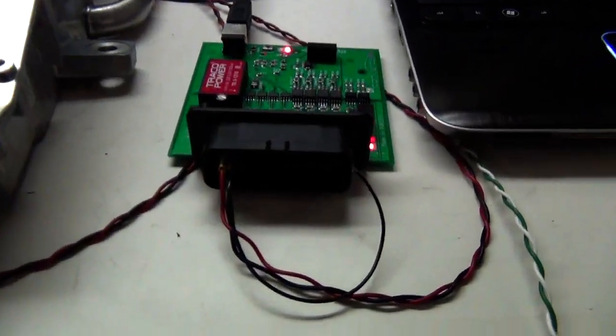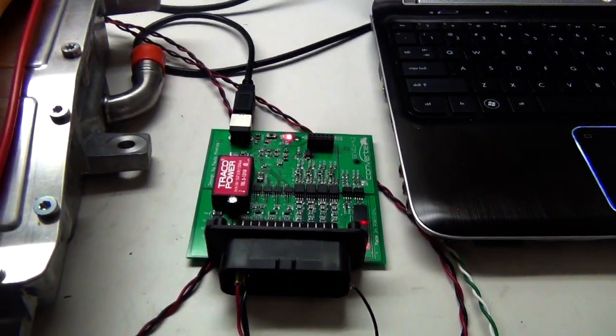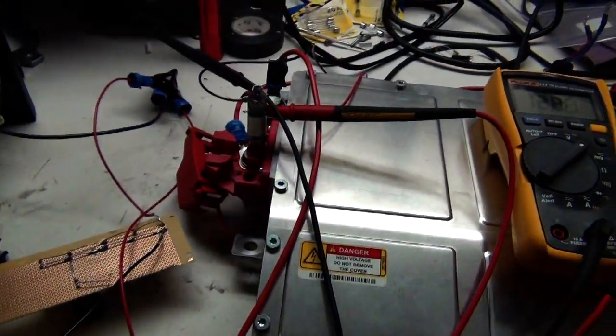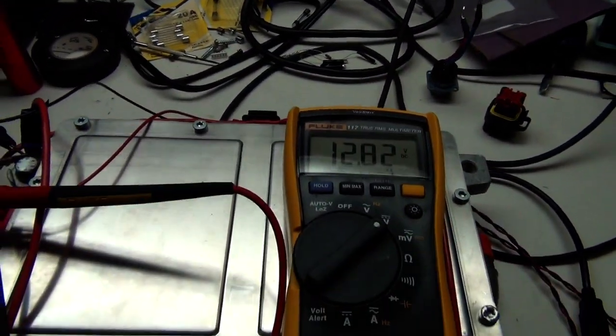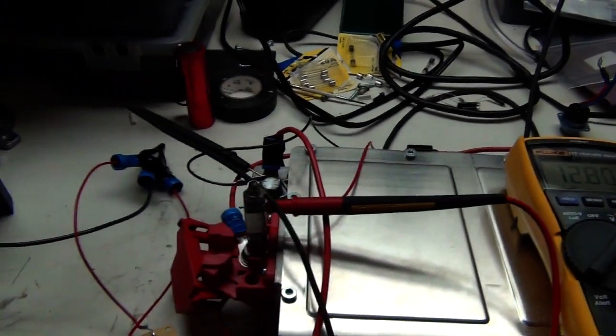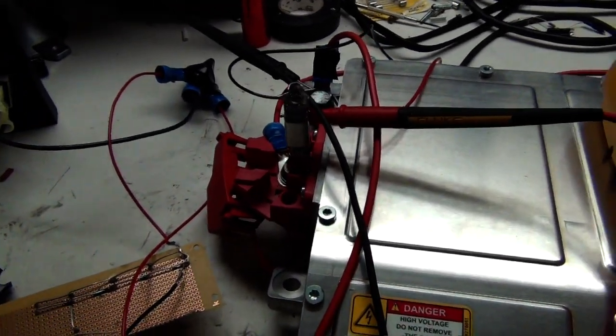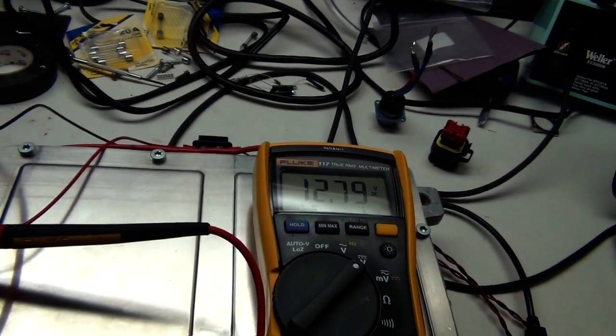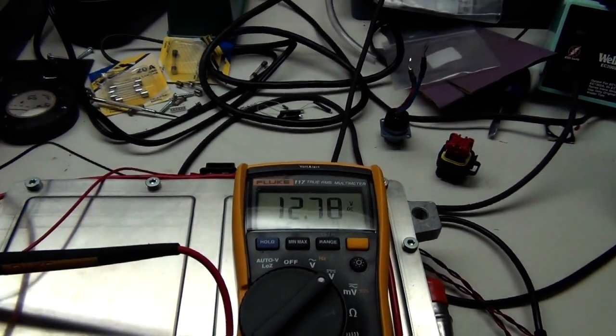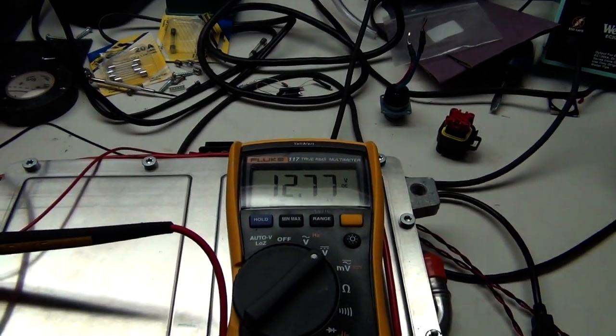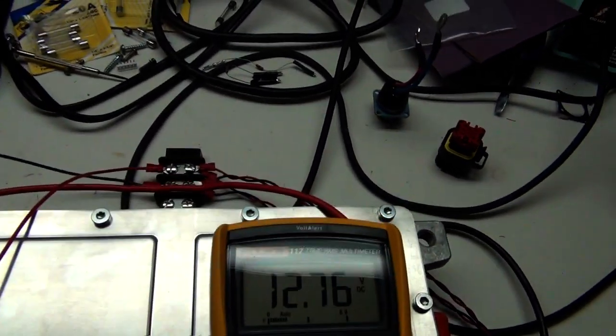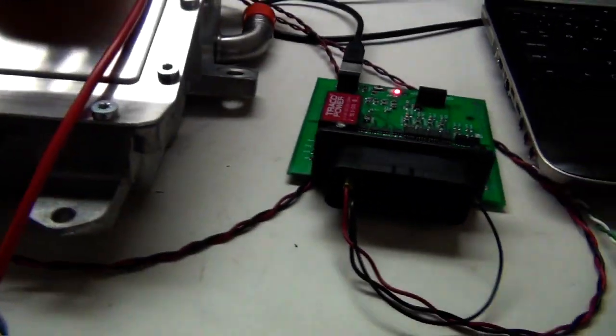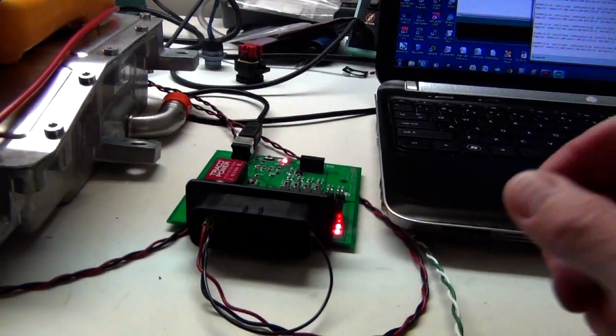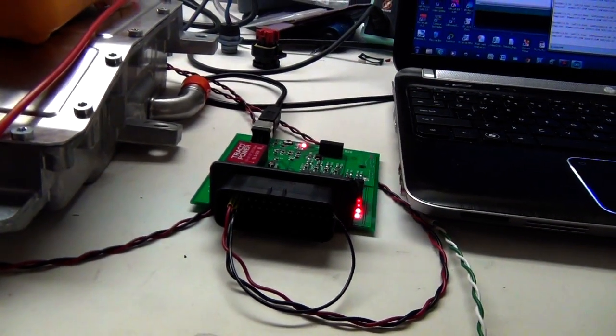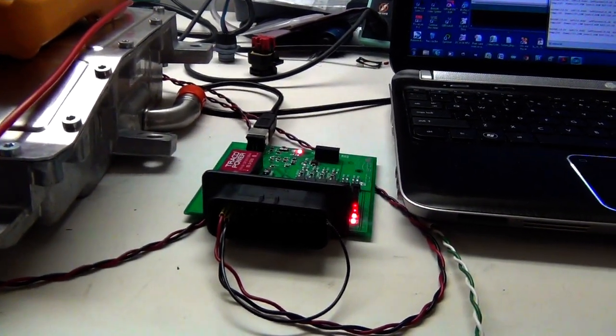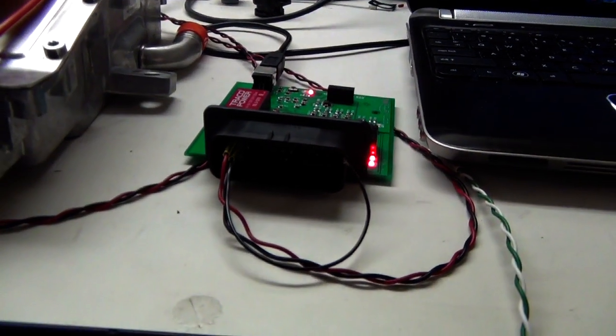So here's the test. I've disconnected the CAN lines, and now the battery voltage came up because it was charged - it's reading 12.8, but there's no output current, because it would be at 13.5. So if I turn on the high voltage, you see there's no output, still at 12.8. So that says you have to have at least some CAN messaging going to get the output to come on. As long as it's connected to the CAN bus all the time, that shouldn't be an issue.